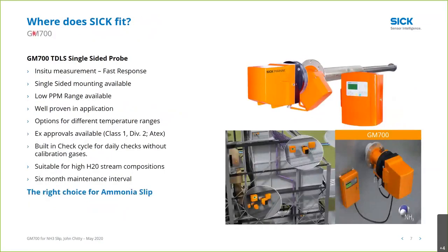So the GM700 TDLS is a single-sided probe. It's an in situ measurement for fast response. It measures in low ppm ranges. It's well proven in ammonia slip applications. We have a lot of these installed. There are different options for different temperature ranges, which we'll take a look at later.